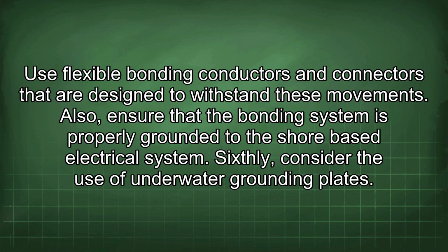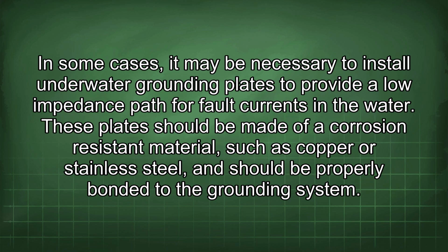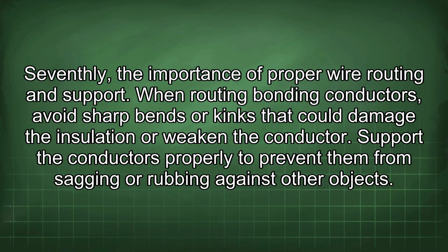Sixthly, consider the use of underwater grounding plates. In some cases, it may be necessary to install underwater grounding plates to provide a low impedance path for fault currents in the water. These plates should be made of a corrosion-resistant material such as copper or stainless steel and should be properly bonded to the grounding system. Seventhly, the importance of proper wire routing and support. When routing bonding conductors, avoid sharp bends or kinks that could damage the insulation or weaken the conductor.